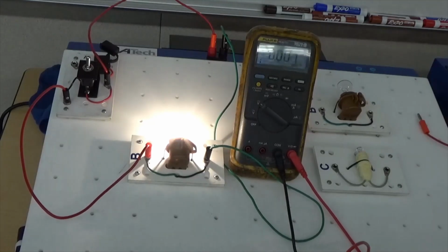Notice, at no point in time did I say that's how much voltage was consumed or dropped. An available voltage check only checks what's available. One lead on the negative, the positive lead on whatever test point you're checking. That's strict.